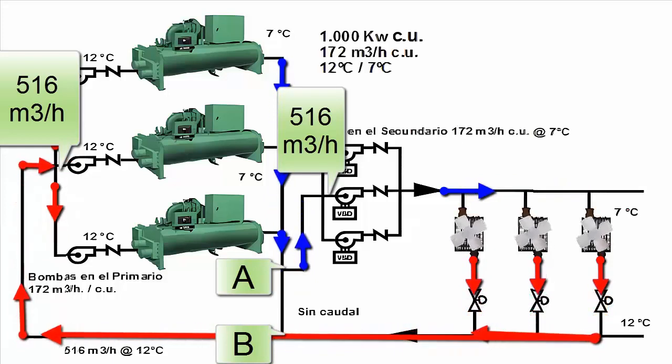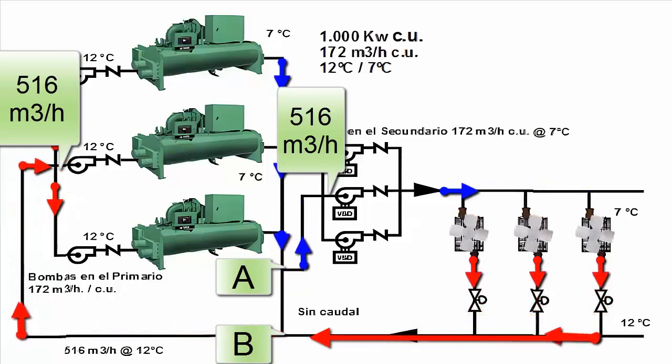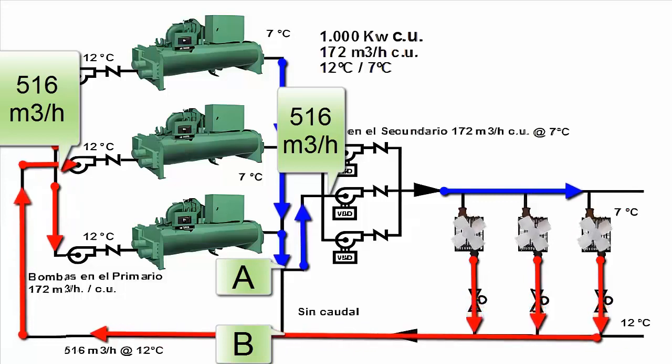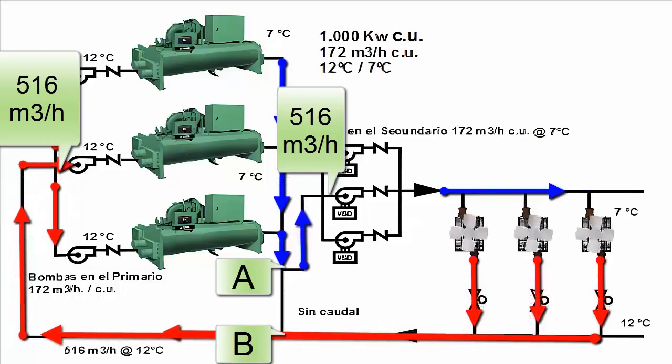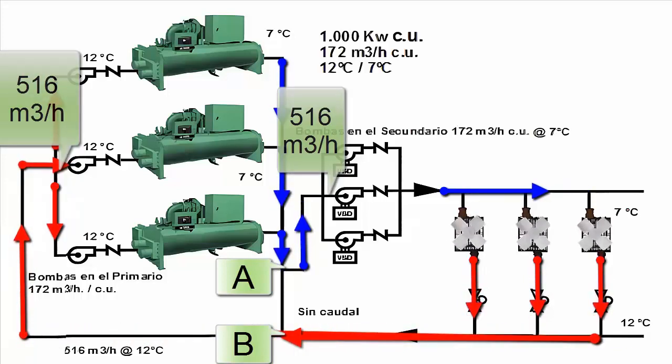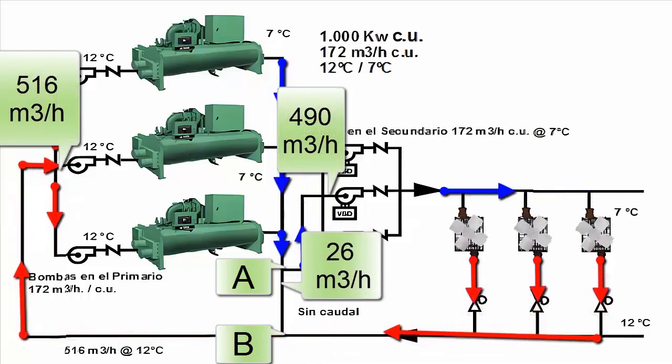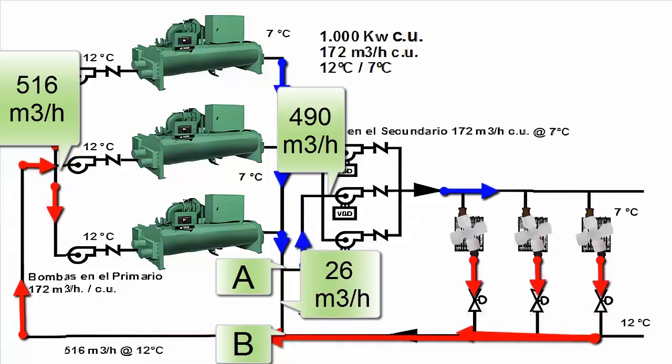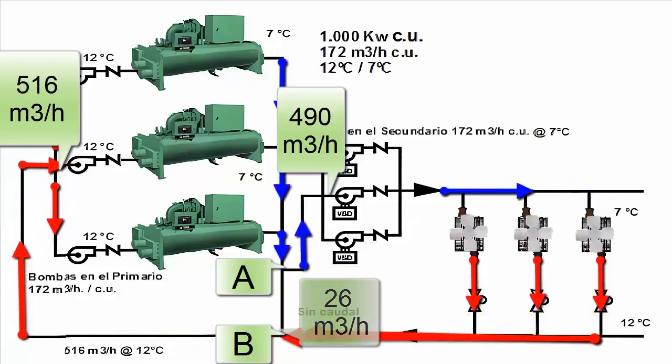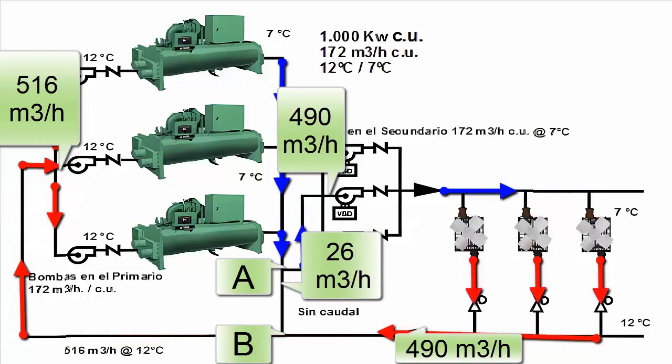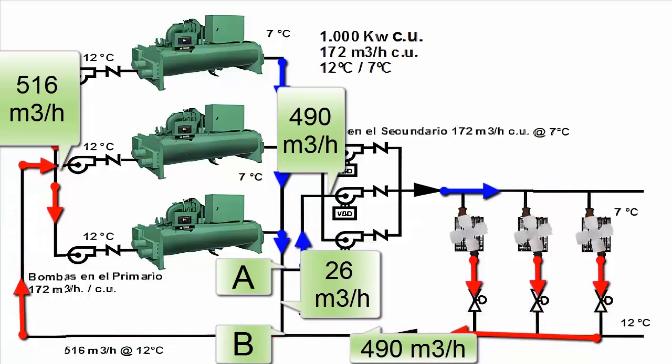Therefore, there is no water flow through this bypass at the moment. However, if the amount of water handled by the chillers is different from that handled by the building's application, there will be excess chilled water flow, which will pass through this bypass to mix with the less chilled water returning from the building, thus avoiding wasting the work of the water chiller.